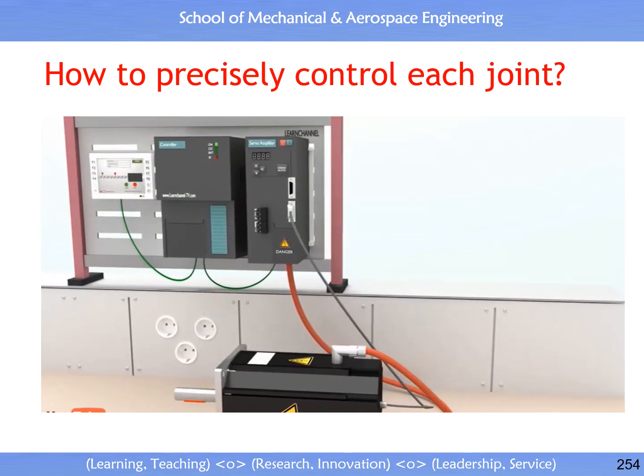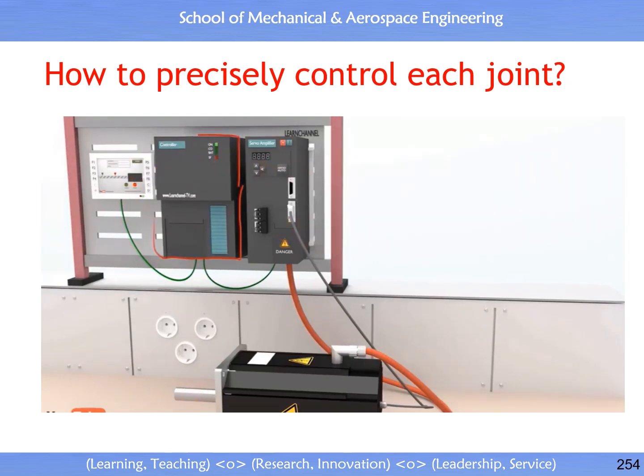The servo motor system includes the servo motor with its feedback device, a servo amplifier, and a controller. But how do these devices work together? The servo controller sends low-voltage control signals for position, speed, or torque to the servo amplifier. Now these commands are amplified up to high power, which the motor can use. The electrical pulses of a sensor are sent back to the amplifier. This amplifier uses this information to control speed and rotor position.